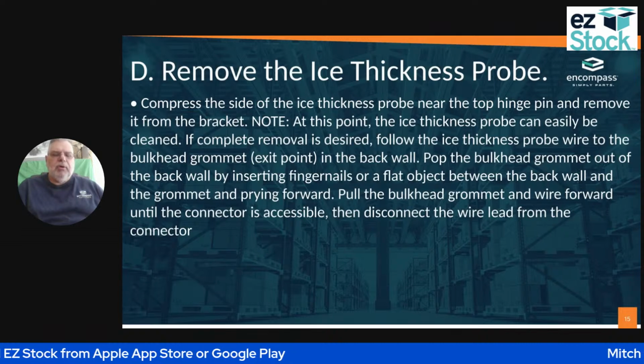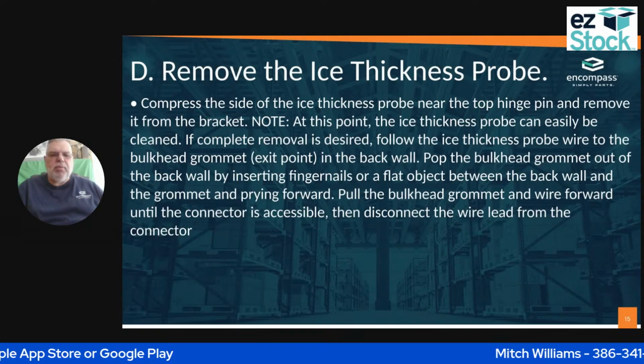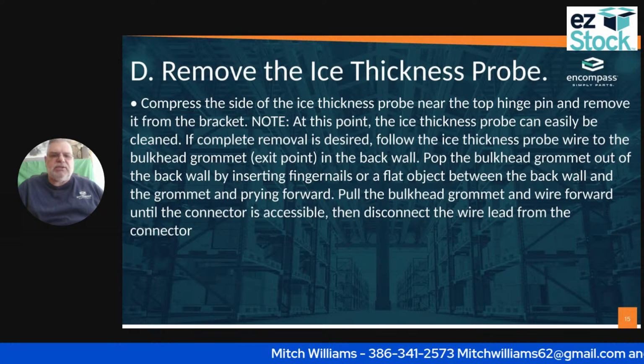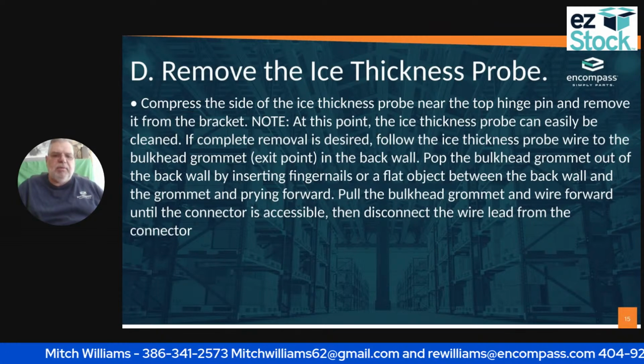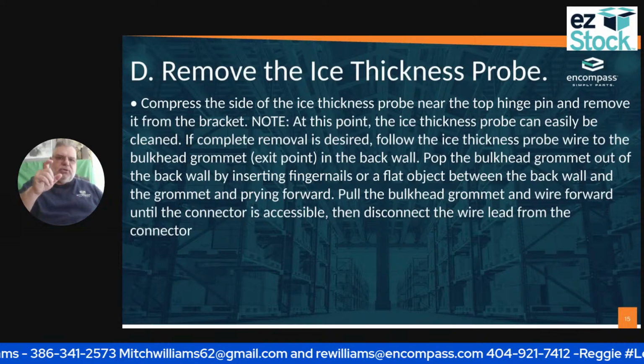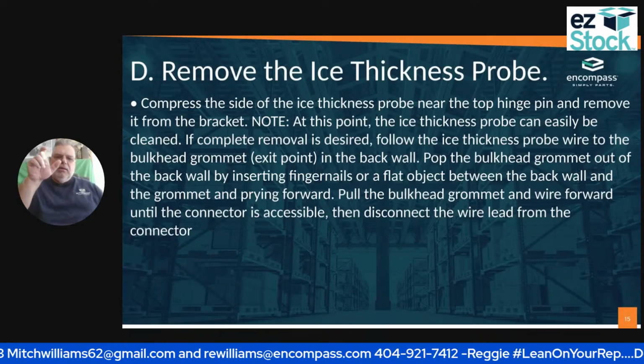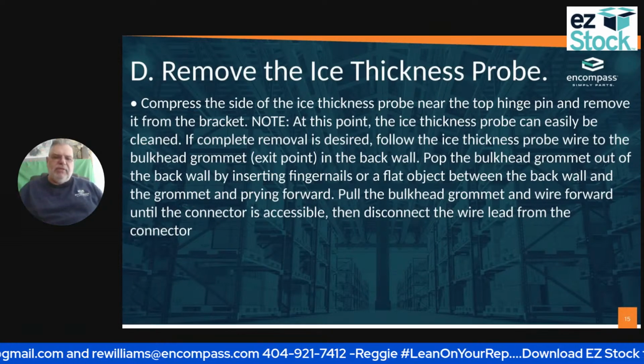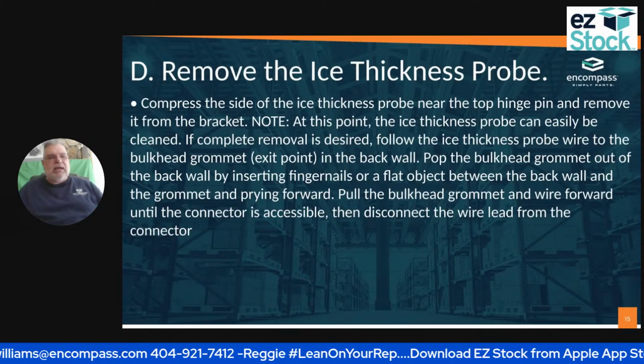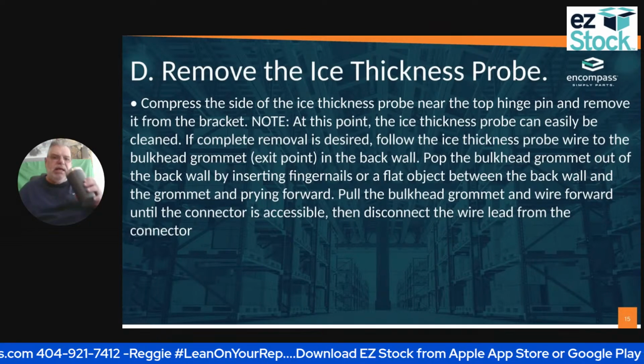I'm going to remove the ice thickness probe. The compressor side of the ice thickness probe near the top hinge, I remove it from the bracket. I pinch those 2 sides on a Manitowoc together and I can remove that. I'm going to save that because I am going to have to sanitize that also.